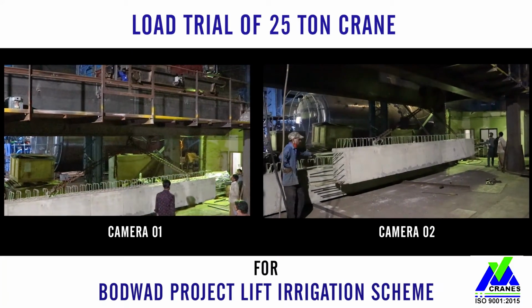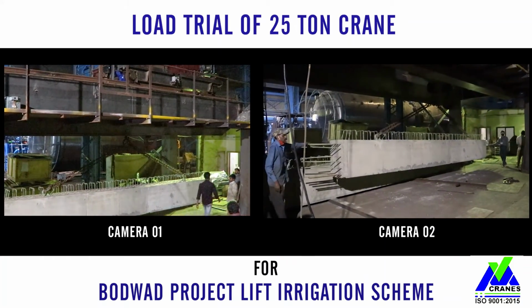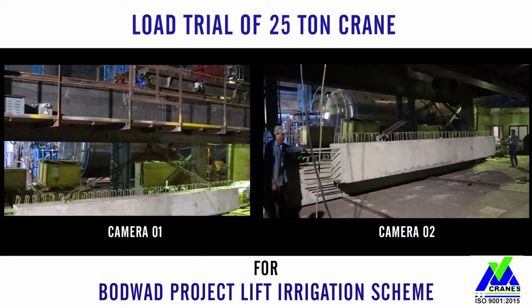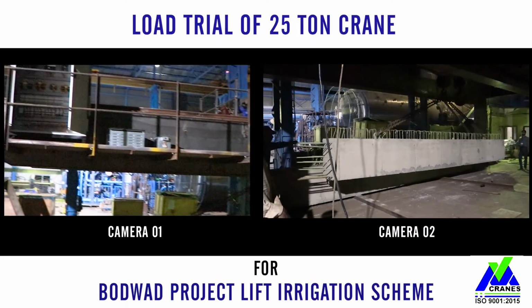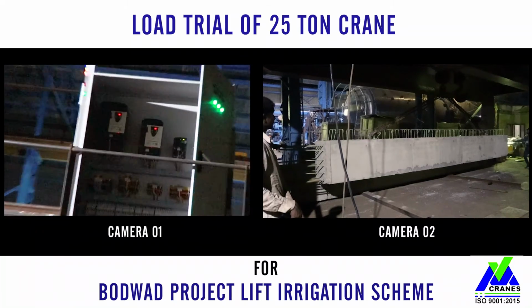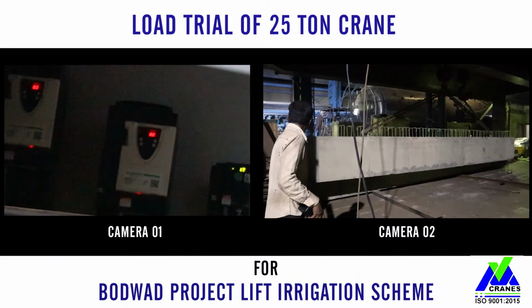For the auxiliary hoist, the current observed is 12.6 amps in the up direction and 10.1 amps in the down direction.